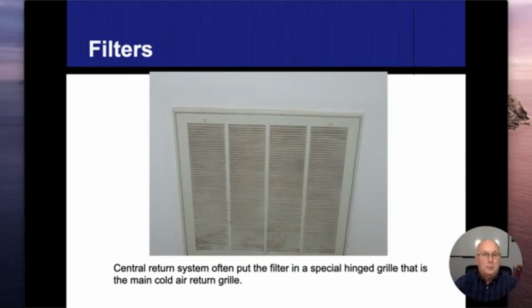One of the measurements I'm hoping you're going to be taking in your system is what we call the delta T, or the temperature change going across the heat exchanger. So it's what they refer to as the temperature rise. We'll find that number on the data plates inside the furnaces. Typically, they're going to be a 30-degree range. And I've seen them anywhere from 25 to 55, all the way up to 55 to 85 degrees. And I'm sure it would be even more than that, but those are pretty much the ranges that I see.